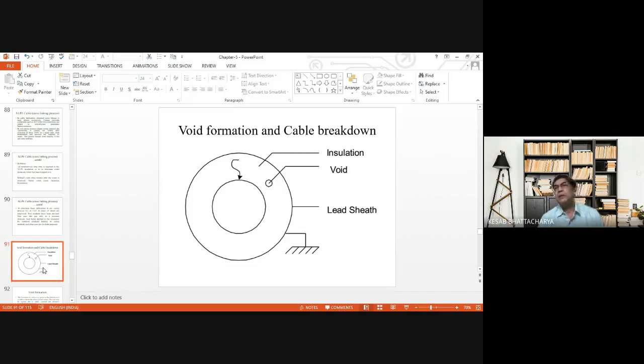After some time, the current or the load through the cable will reduce, because the load is not constant at its maximum value all throughout the day. Sometimes it reaches its peak values and remains constant at the peak value for some time, but before or after that, loads will be less than the peak value. Therefore, the expansion of the insulating material placed over the conductor core due to heat generation will be maximum when the load is maximum. But when the load reduces, what really will happen?